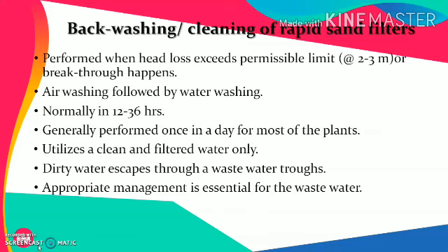backwashing is performed. The backwashing is generally performed first in the form of air washing followed by the water washing as we have discussed. The backwashing is generally done once in a day for most of the plants, even though it should be performed normally in a range of 12 to 36 hours depending upon the clogging and the need. But generally most of the water treatment plants around are performing the backwashing once in a day.